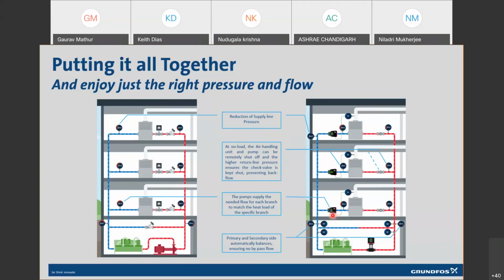So essentially, these pumps are connected in parallel with individual NRVs to ensure the backflow is not there. And the supply side pressure being lower is essentially what makes the system self-balancing. But we will look at it from a hydraulic gradient diagram, because visualization is the best way to understand things. So when we look at the hydraulic gradient diagram, you will really understand where the pressure losses are eliminated in distributed pumping and how you actually see the savings.